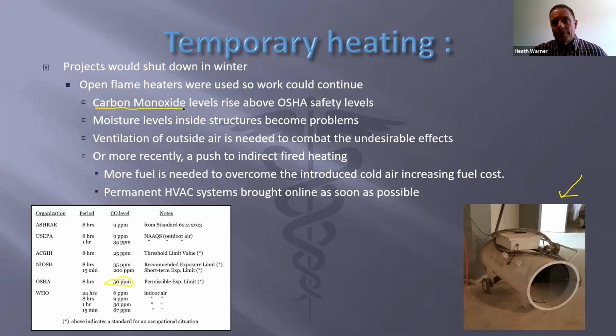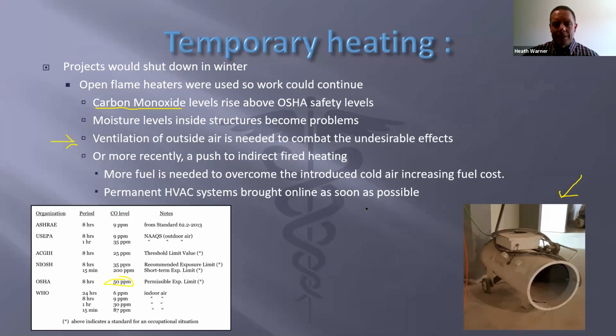Trouble with that is, and if you've ever done volume calculations on most construction sites, you cannot produce enough heat to maintain a building at between 50 and 60 degrees for finishes that are going to be safe without introducing ventilation from the outside. Not to mention, moisture levels inside from that combustion process create a whole other host of issues. But that ventilation from the outside means you're going to pump in cold air just to bring down the CO level within the building, which means you need more fuel to overcome that.